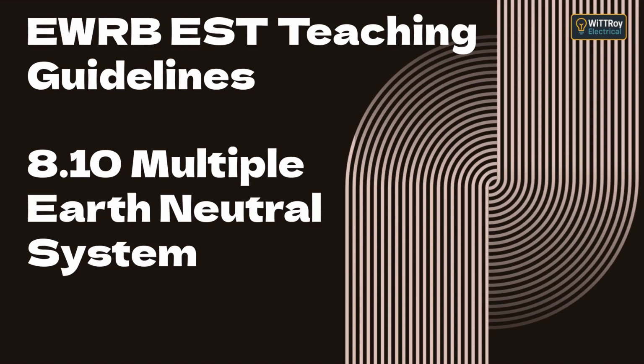Topic F, the effects of a missing MEN link. The MEN link connects the neutral bar to the earth bar at the main switchboard. If it's missing, broken, or loose, the system can become extremely dangerous. Here's what happens. Fault current can't return properly to the source. The circuit's voltage to earth readings become unstable. Metal parts of appliances or switchboards can become live because the neutral is no longer at earth potential. With no MEN link, earth fault loop impedance increases, which delays or prevents the circuit breaker from tripping. Always check the MEN link during testing, it's small but vital for safety.